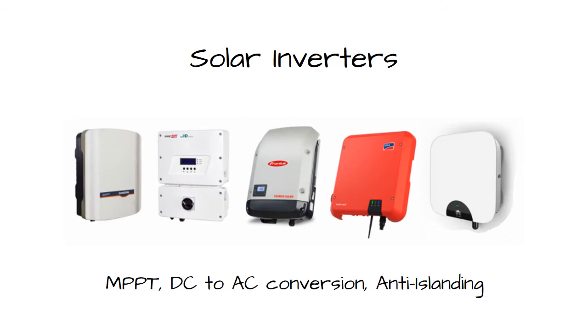MPPT is performed by the solar inverters, which are connected to the panels. These are some popular brands courtesy of Clean Energy Reviews. Besides MPPT, the function of the solar inverter, or PV inverter, is to convert the variable DC output of solar panels into AC so that the electricity can be fed into a commercial electrical grid. In North America, the output is 240 volts AC at 60 Hz. In Europe, the output is 230 volts AC at 50 Hz. The current will vary with the outputs from the panels.